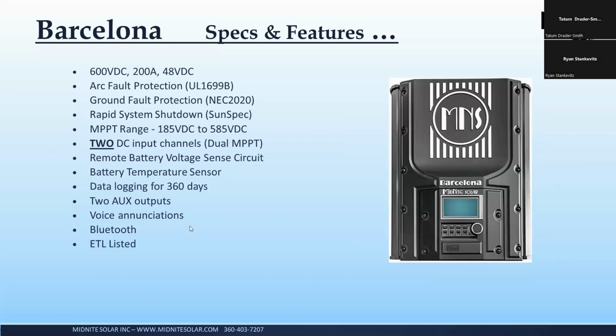And as such, every negative in the system is now considered current carrying and requires a disconnect and overcurrent protection as well, meaning everything has to be 2-pole breakers. So with the new ground fault protection, we're looking for differential current, sort of like a grid tie inverter, between positive and negative, that allows you to solidly ground the battery negative and make the system a lot safer, in my opinion. So that's kind of a nice feature. The arc fault protection comes with the ground fault protection. It's a kit. We'll show you here in a minute, but you get a circuit board and a couple CTs that go in the device.